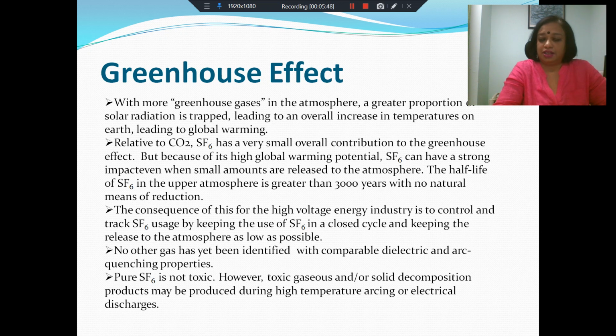Unfortunately, even though there is a lot of research going on, we still do not have a viable alternative to SF6 that has the same kind of high dielectric breakdown strength or equivalent arc quenching properties. So we don't really have an alternative. Various alternatives have been tried, for example, SF6 mixed with other inert gases such as nitrogen, but we are still not in a position to give up on SF6. Another important thing is that pure SF6 is not toxic, so it's not a problem.